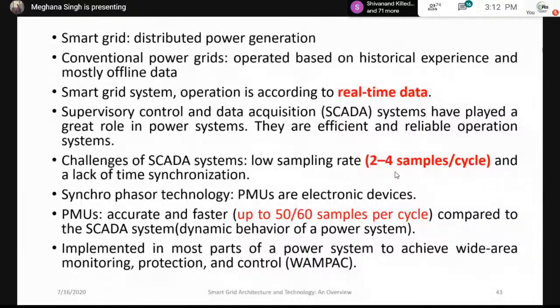The challenges associated with SCADA are the low sampling rate, that is 2 to 4 samples per cycle, and the lack of time synchronization. This is not acceptable, and it leads to a lot of problems later on. I don't want to work at such low rates, 2 to 4 samples. I need to work at 50 or 60 samples per second. That can be done with the help of PMUs, which are basically electronic devices. They are accurate and fast, and very fast when compared to SCADA.